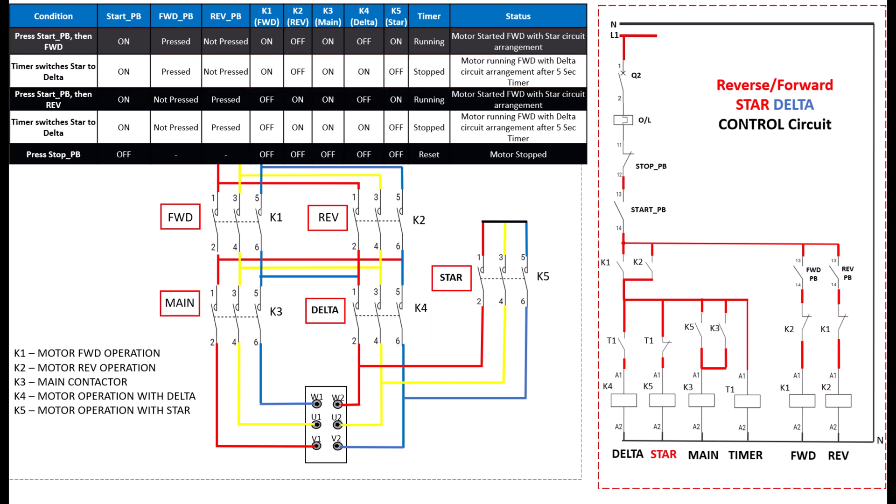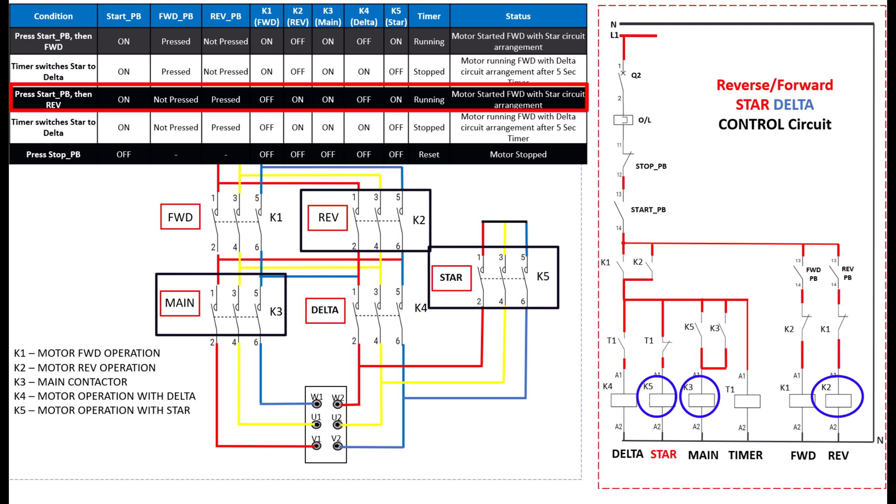Now case two. You need to run the motor in reverse direction with star configuration and then delta configuration. When you press the start push button followed by the reverse push button, what happens? K2 reverse contactor, K3 main contactor, and K5 star contactor engage. The motor starts running in the reverse direction using the star configuration. After five seconds, the timer deactivates K5 star contactor and energizes K4 delta contactor through the interlock. Now the motor continues to run in the reverse direction in full delta mode.